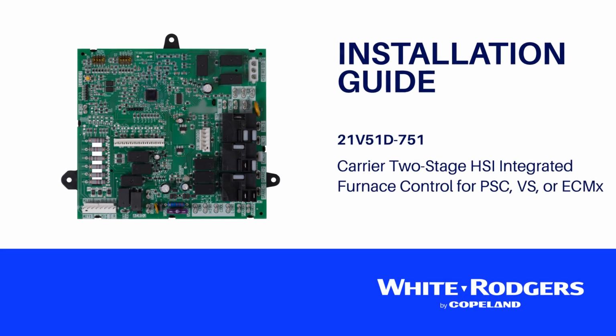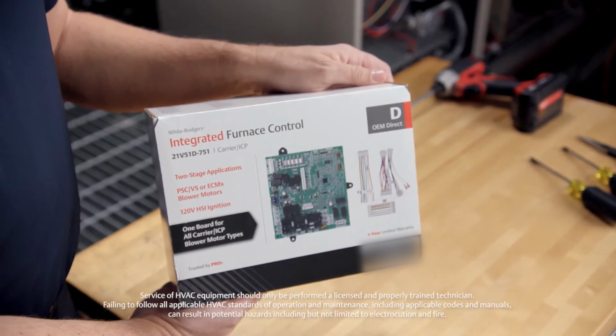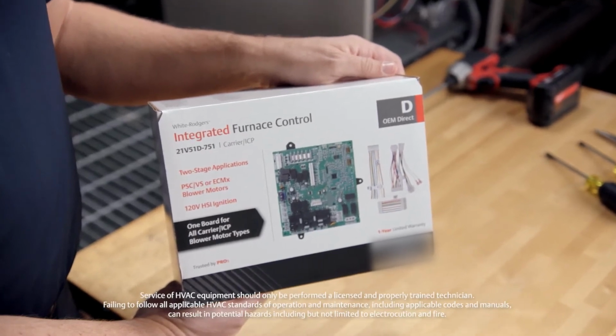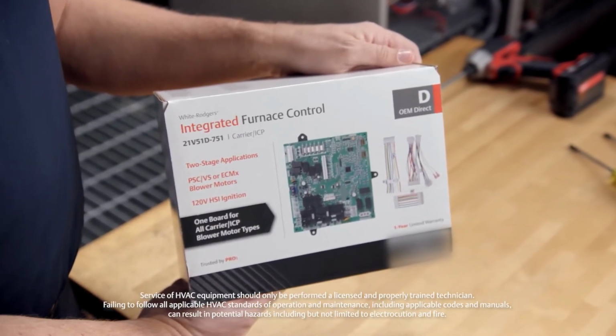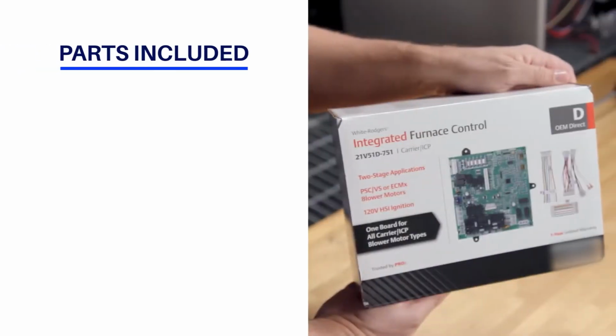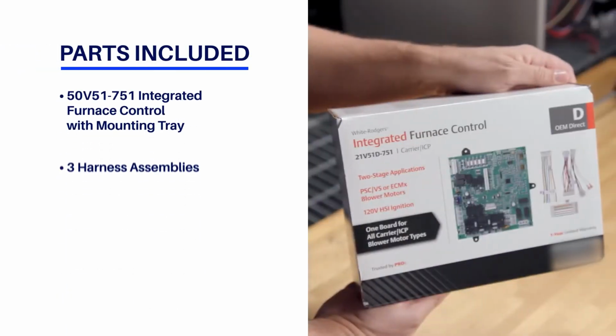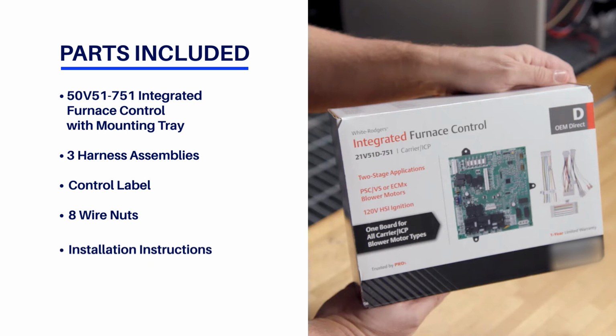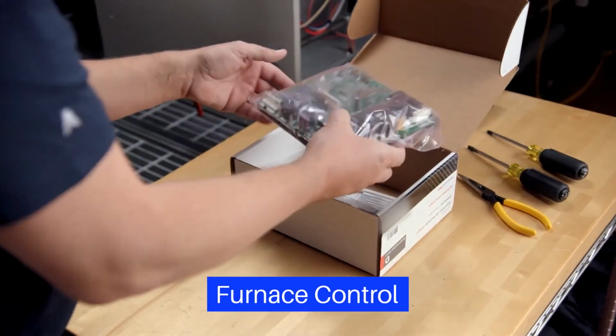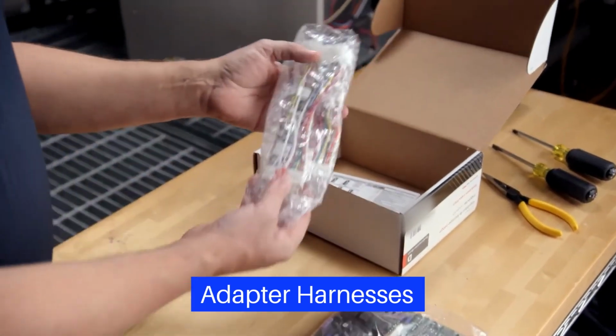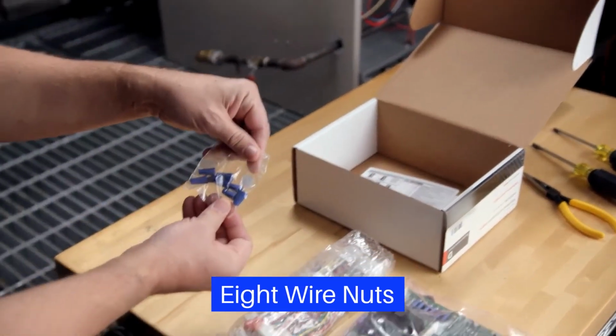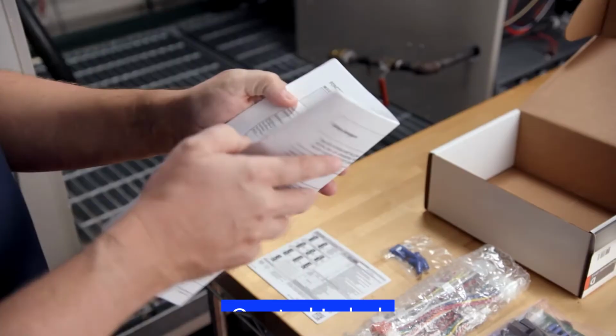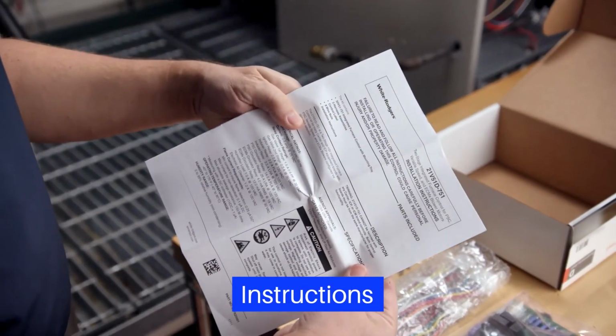This is the installation video for the White-Rodgers 21V51D-751 Carrier 2-stage integrated furnace control for PSC, ECMx, and variable speed blower motors. The kit includes materials needed to replace a 2-stage control for Carrier and ICP branded equipment for PSC, ECMx, and variable speed blower motors. The box includes a furnace control with mounting tray, 3 adapter harnesses, 8 wire nuts, a control label, and instructions for easy installation.